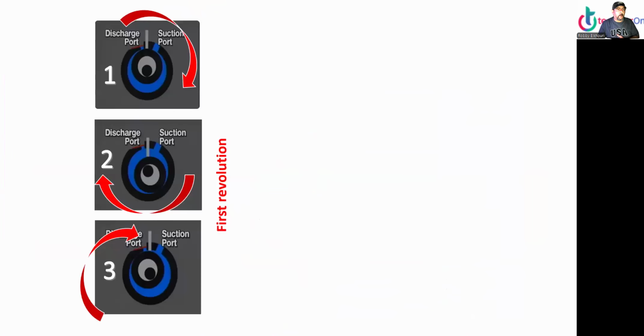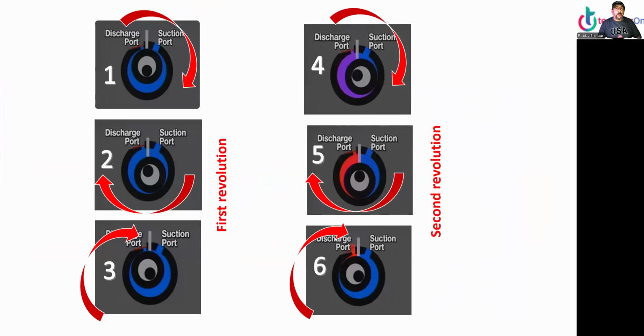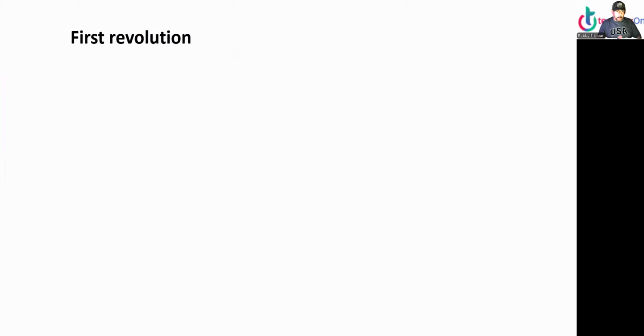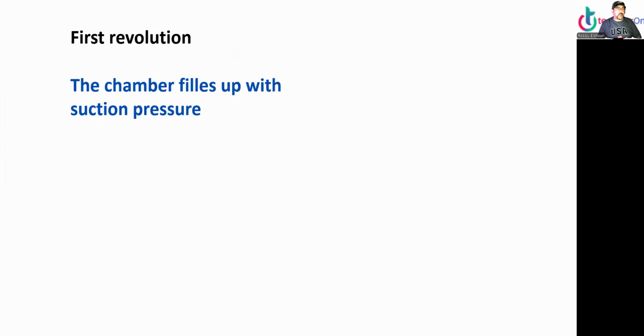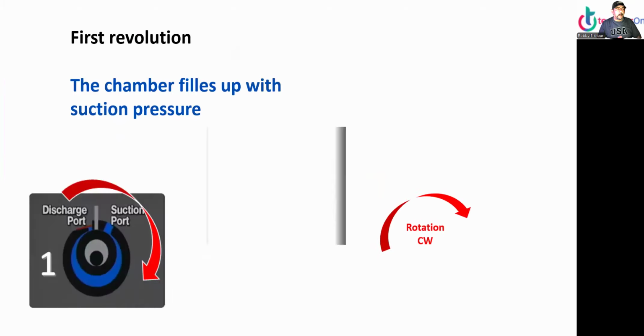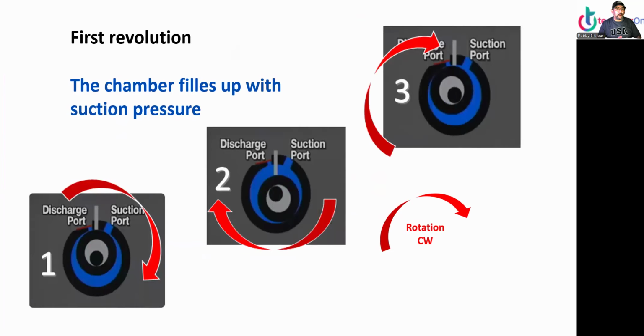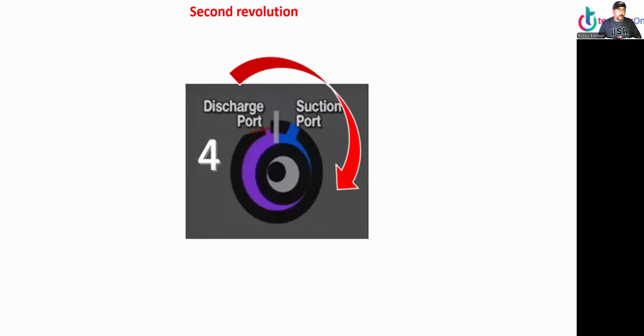Clockwise rotation. We have the first revolution, which fills up with vapor, no compression, it just fills up. And then the second revolution, we'll cover it. First revolution, the chamber will fill up with suction pressure, rotation clockwise, 1, 2, 3. As you can see, it fills up the chamber. Second revolution, now as you can see, the pressure starts to increase, medium pressure.